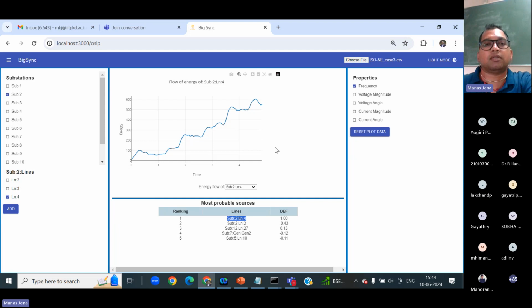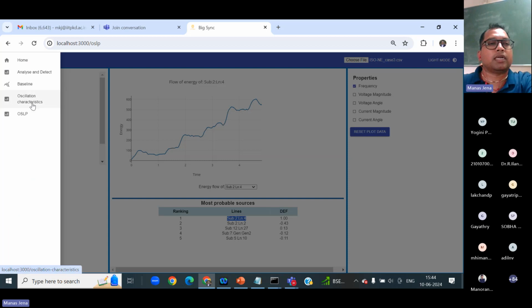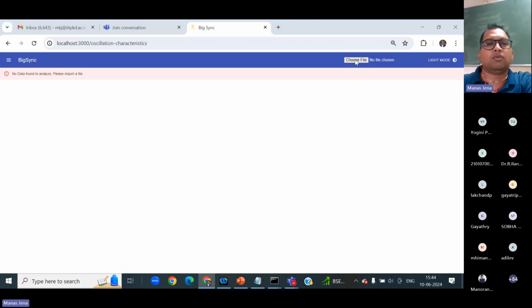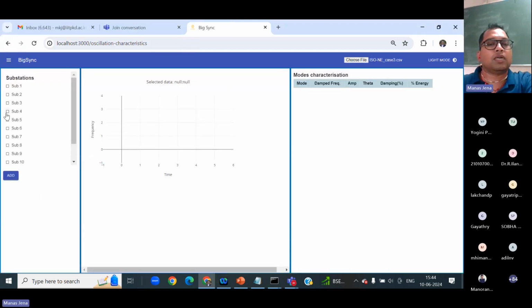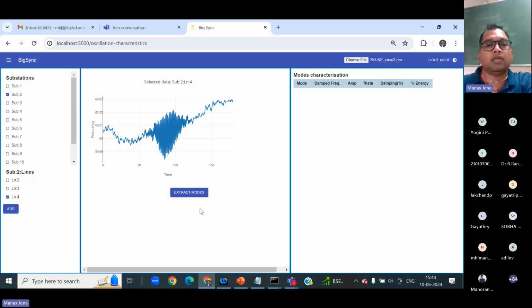What is the frequency of oscillation? What is the damping? So for that I need to go to this oscillation characteristics. So again you go to that, import the test case. So what the previous program said, that there is an oscillation coming from substation 2 line 4, right? You add, then click extract modes. So we have developed some algorithms which are integrated, which will extract the modes from the signal, and then it will show, okay, you have these modes and the corresponding frequency of oscillation, amplitude and damping.